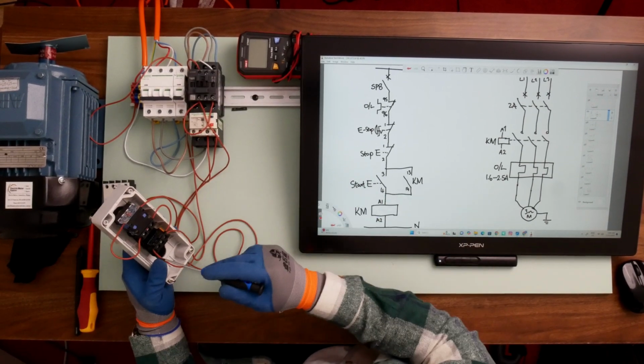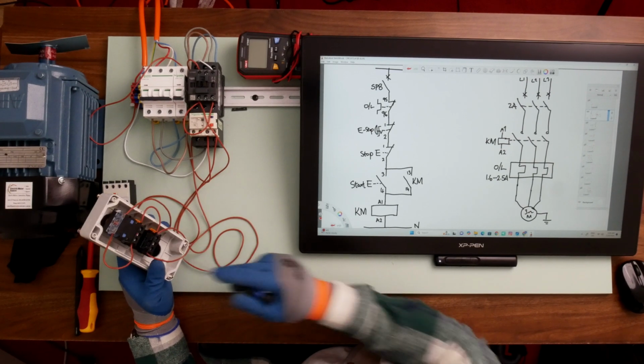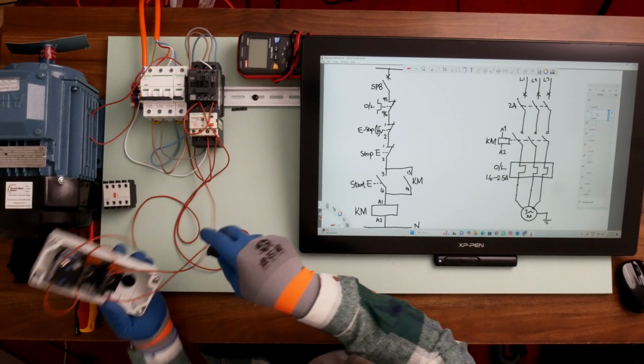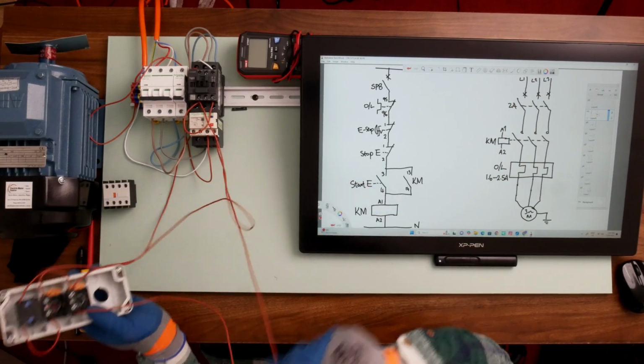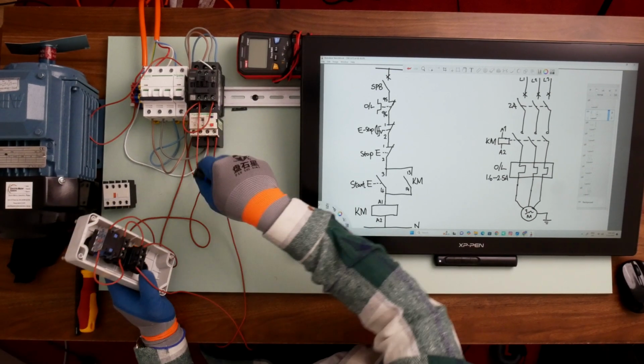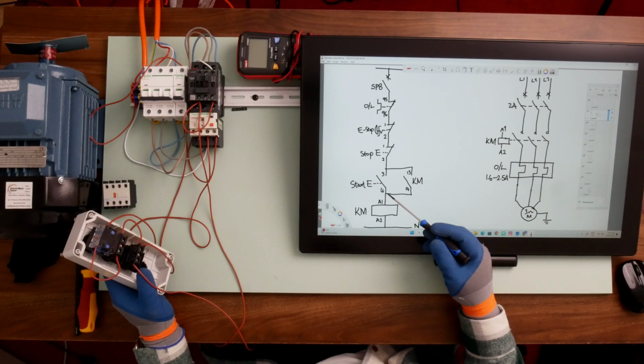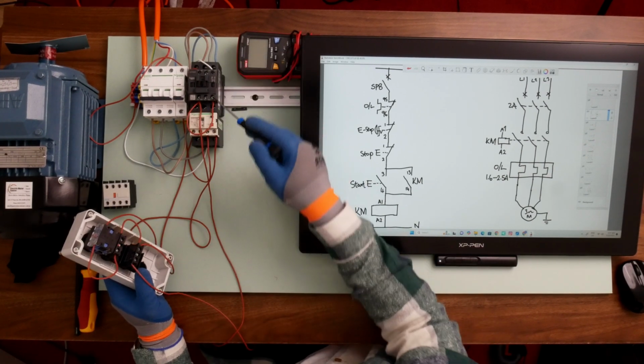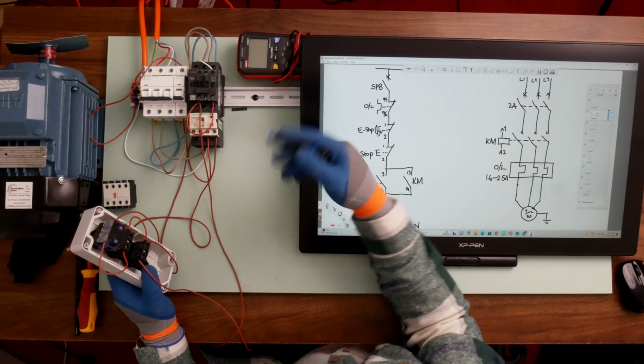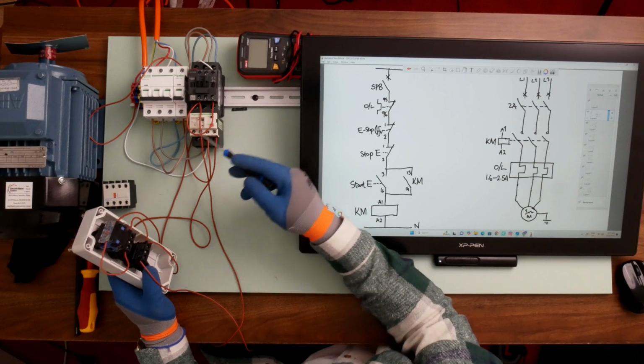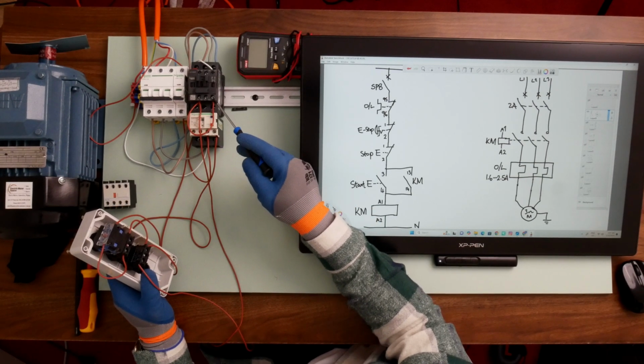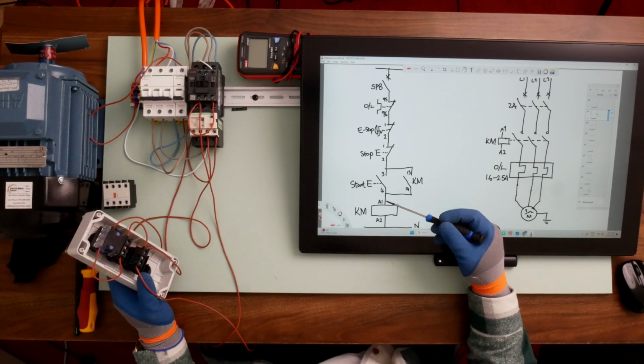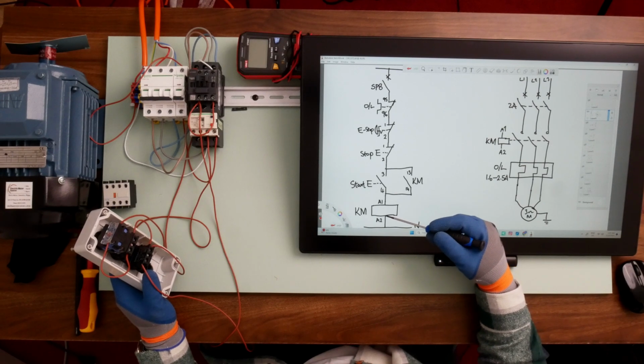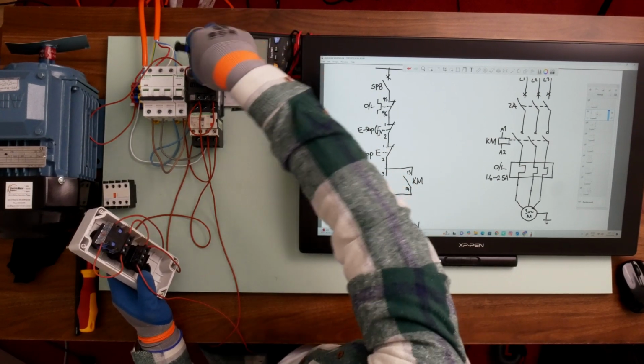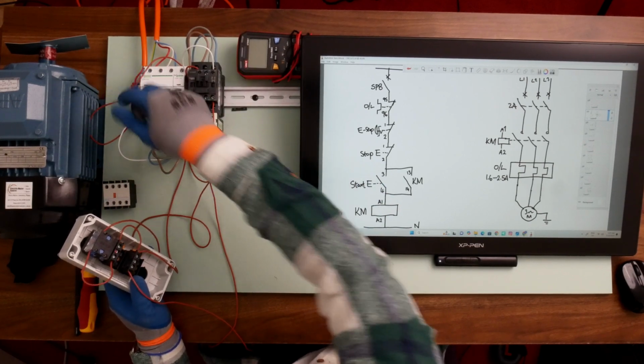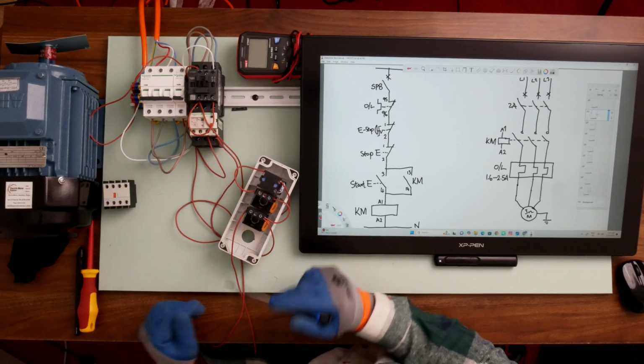And then from the bottom of my start push button, on 4 on my push button, I have another wire that is going to 14 on my auxiliary contact. This is the one that's going to 14, and 14 here on my auxiliary contact is the same point as A1 on my contactor. So I've conveniently connected to A2, because A1 or A2 doesn't make any difference. You just connect to whichever is convenient or closer to 14. So I've connected here to one terminal of the contactor coil. This connection is already there. Now I'm left with the other connection that goes to neutral. I've taken it off A1, and then it goes to my neutral connection, which is on the blue terminal here. So basically, everything is pretty much covered.